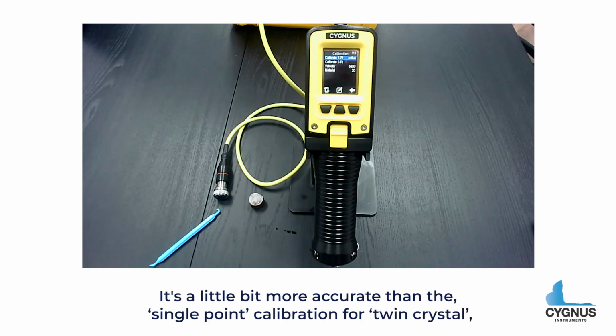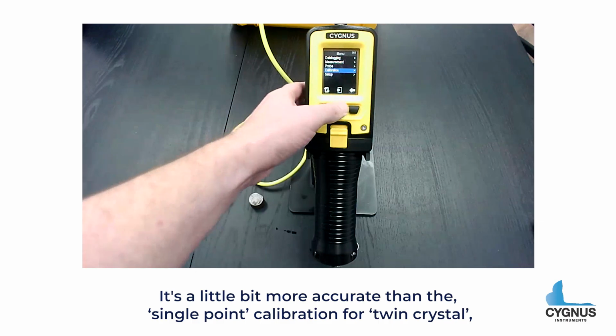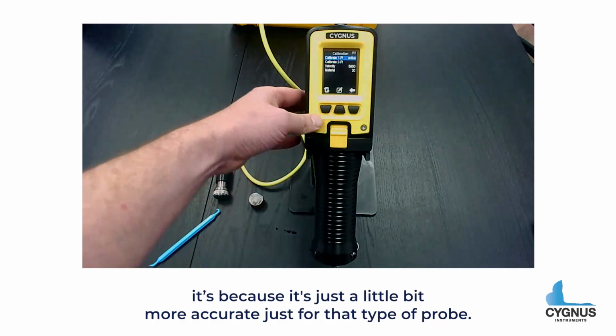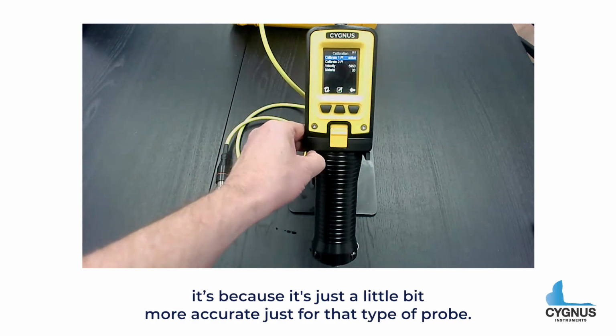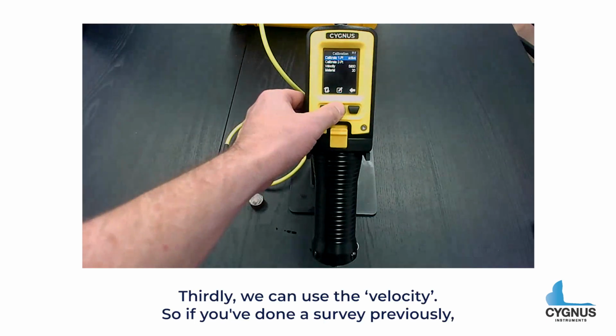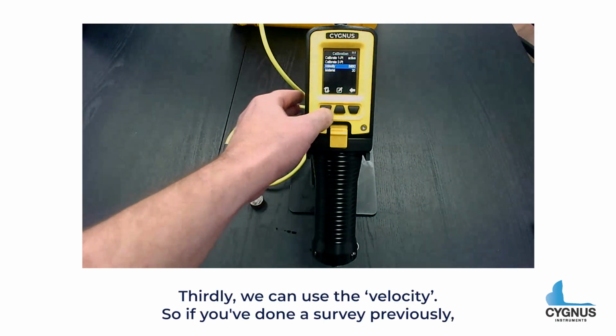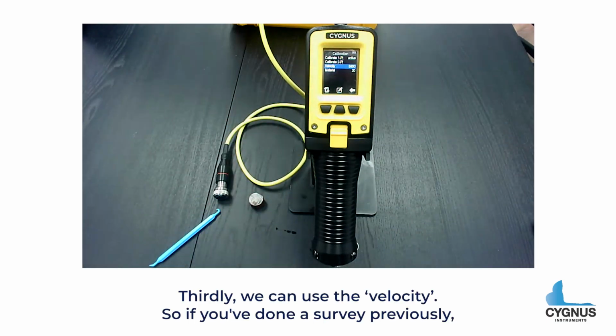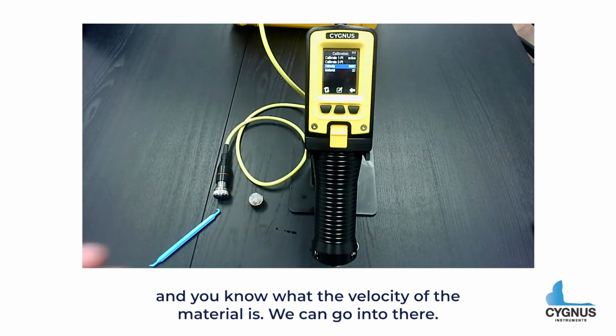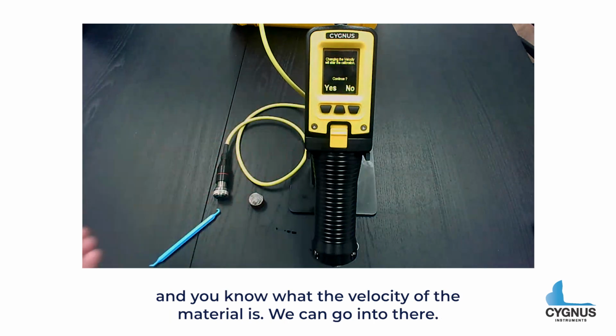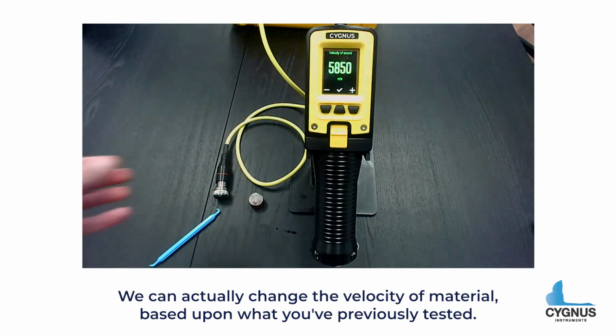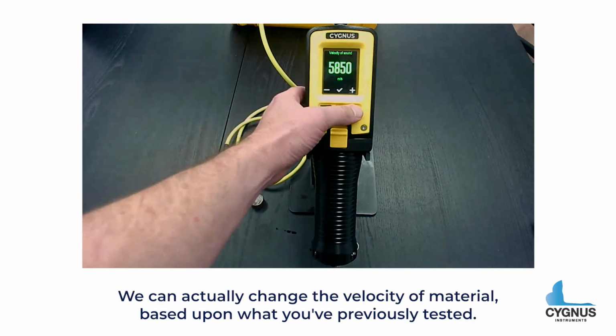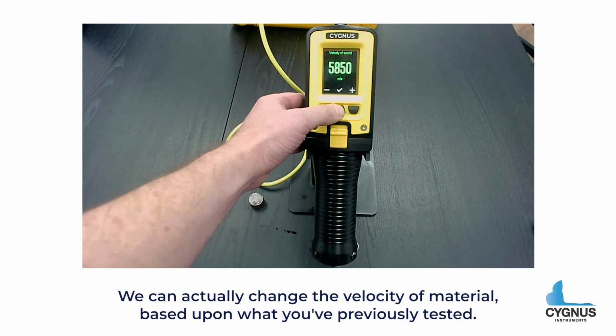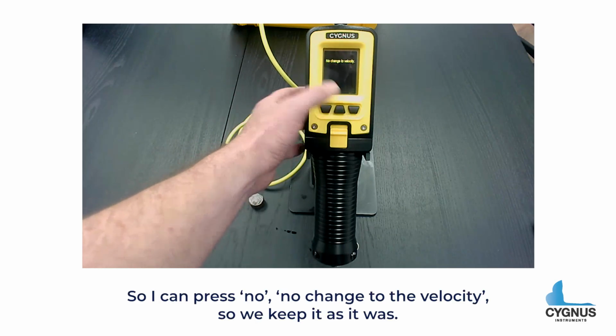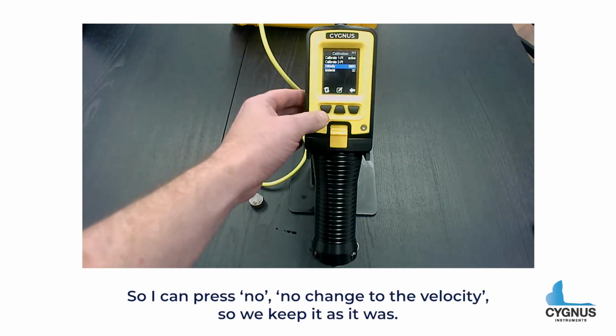Secondly, we can calibrate via the 2-point calibration, which is only for the twin crystal probe. It's a little bit more accurate than the single point calibration for that type of probe. Thirdly, we can use the velocity. So if you've done a survey previously and you know what the velocity of the material is, we can go in there and change the velocity of the material based upon what you've previously tested. So I can press no change to velocity, so we keep it as it was.